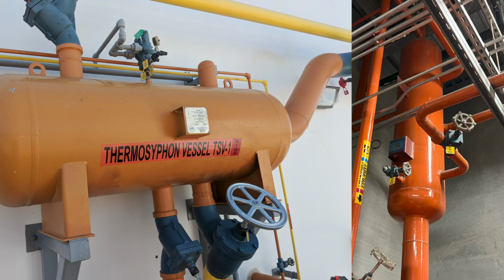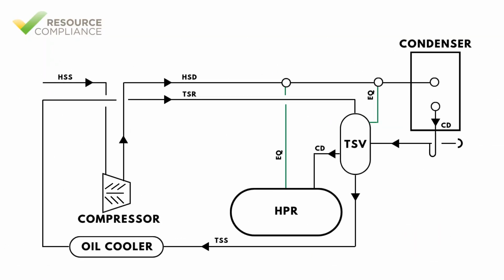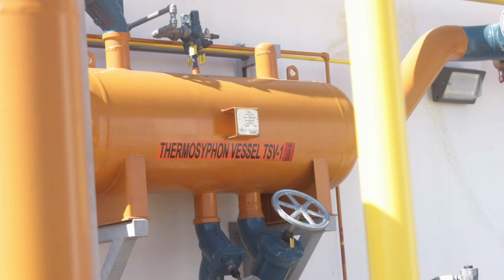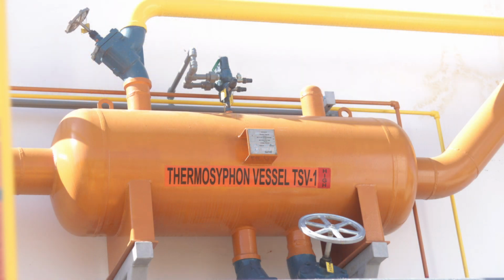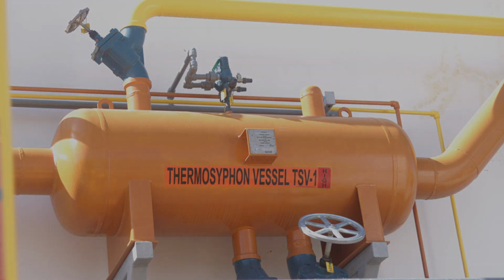Thermosyphon receivers can be designed for both horizontal and vertical orientation. In either case, liquid from the condenser enters the thermosyphon vessel before the high-pressure receiver. Overflow from the thermosyphon vessel drains directly into the HPR. Equalizer pipes connect both vessels to the compressor discharge main, which means that they operate at the same condensing pressure. Thermosyphon vessels have minimal valves and sometimes do not even have sight glasses. As a result, these vessels are mostly maintenance-free, except for periodic visual inspections.